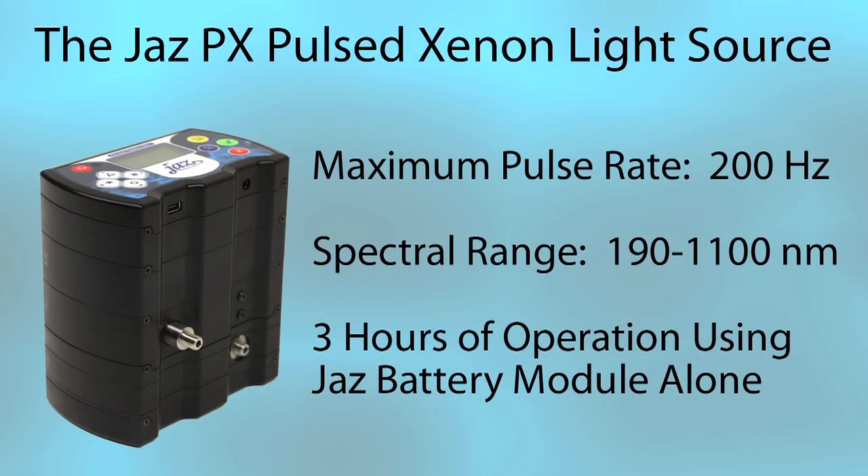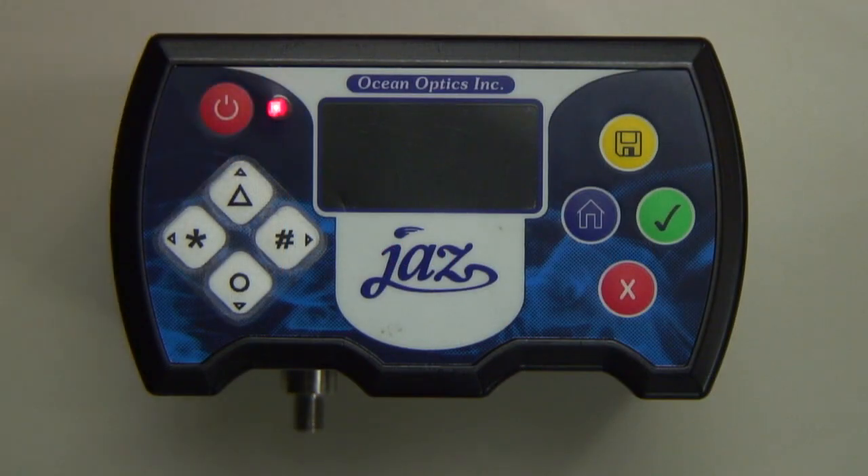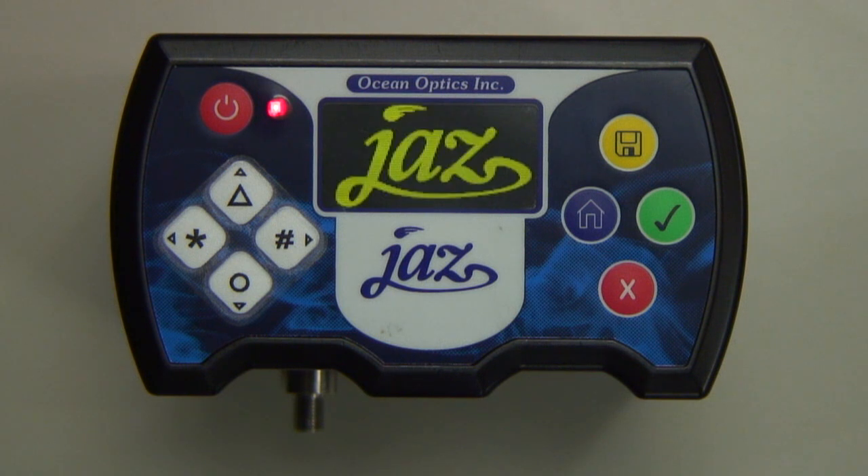The Jaz PX pulsed xenon light source has a maximum pulse rate of 200 Hz, a spectral range of 190 to 1100 nm, and can operate for up to 3 hours on the Jaz battery module alone. It's important to recognize the different power modes offered on the Jaz Spectrometer.